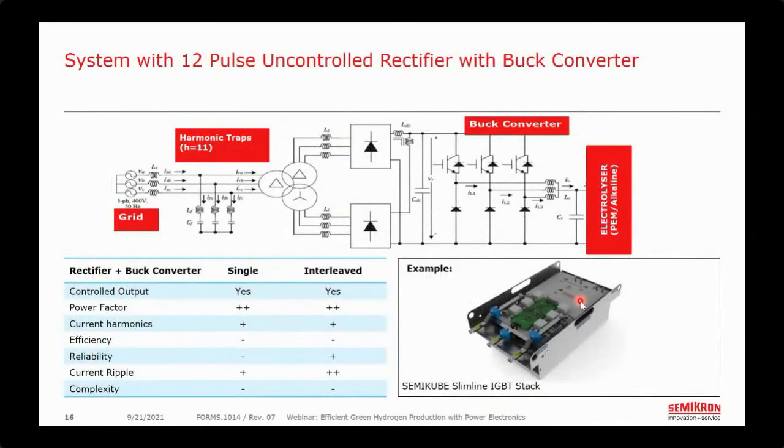Here in this picture, we show what a system topology can look like. On the electrolyzer side, you have the three interleaved buck converter, and a 12 pulse uncontrolled rectifier for rectifying from AC to DC, connecting to the transformer and passive filter. That could be a system using IGBT for the buck converter.